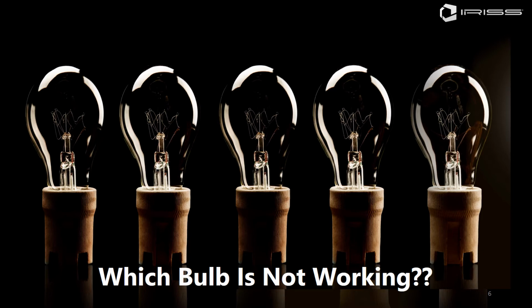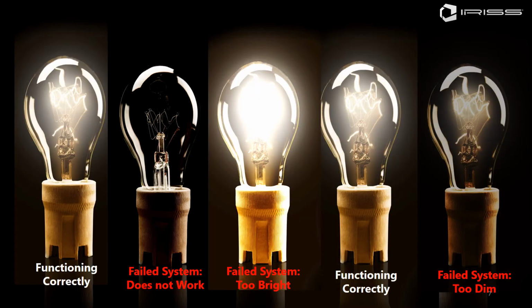Obviously, there are long-winded ways of testing these, or we can do resistance tests, etc., just to verify that, but the most simple method of testing these is to switch them on. Once they're switched on, you can see bulb number 1 is functioning correctly. Bulb number 2 is complete system failure, zero light. Bulb number 3 is working, but it's much too bright, so it's still classed as a system failure. Bulb number 4 is functioning correctly. And bulb number 5 is working, but it's too dim, so it's still a system failure.